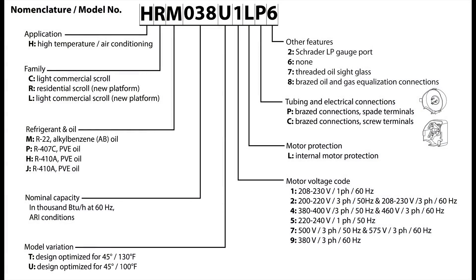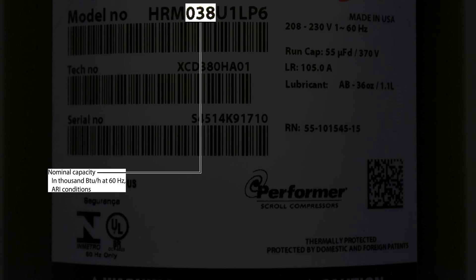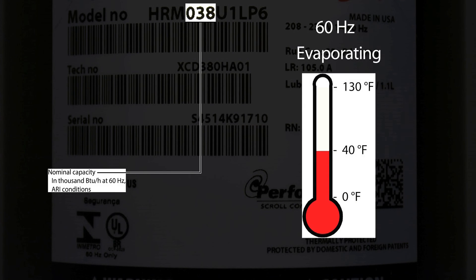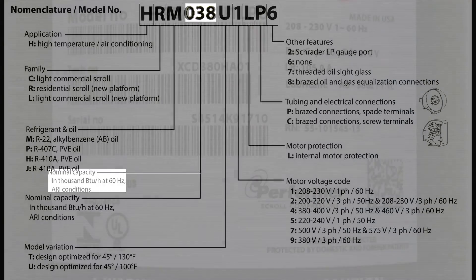The next three digits of the model number signify the nominal capacity of the compressor in thousands of BTUs per hour. The nominal capacity is determined by using standard AHRI conditions at 60 Hz, with 45 degrees Fahrenheit for the evaporating temperature and 130 degrees Fahrenheit for the condensing temperature.